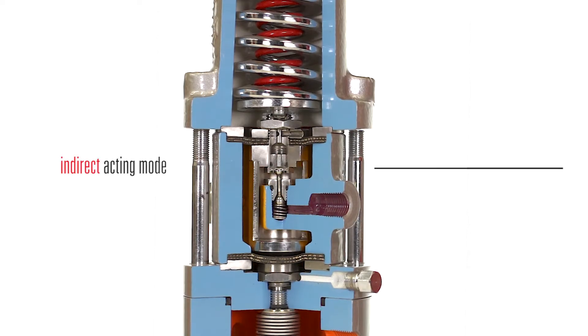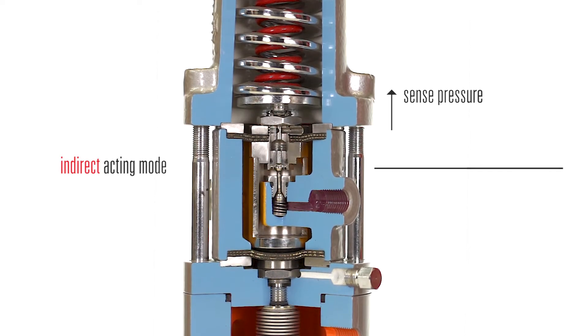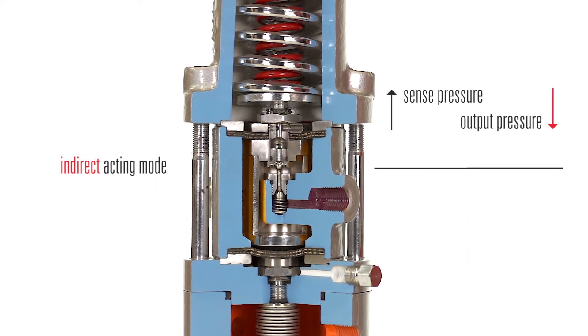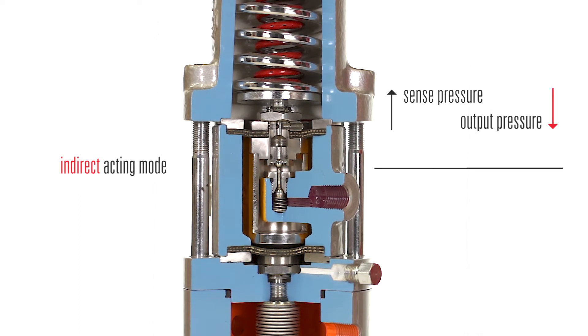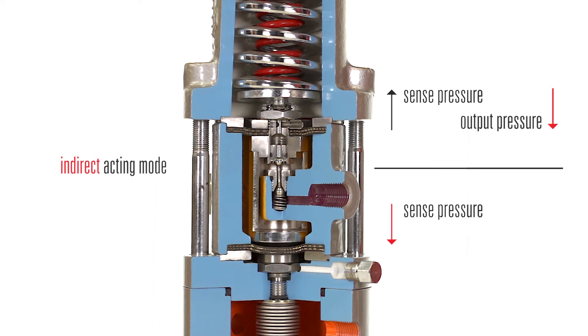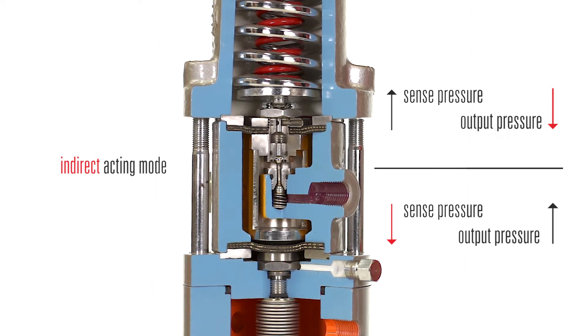When it is in indirect acting mode, an increase in sense pressure will decrease output pressure to the valve, while a decrease in sense pressure will increase output pressure to the valve.